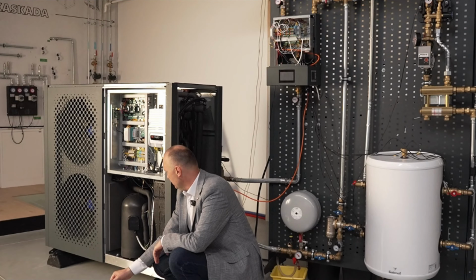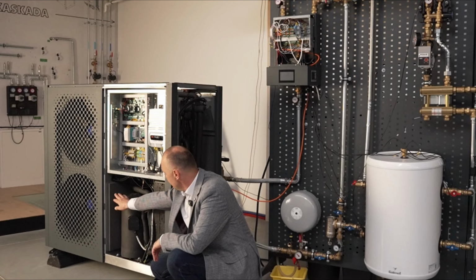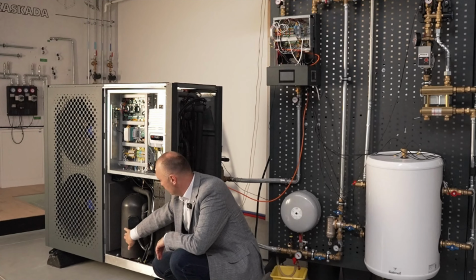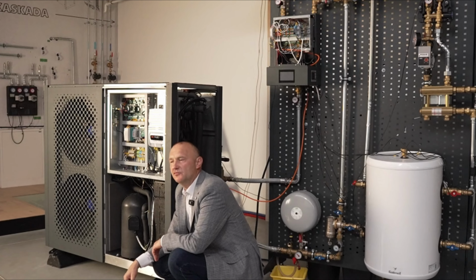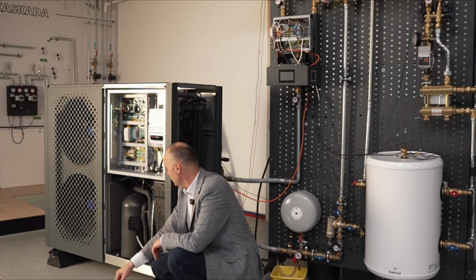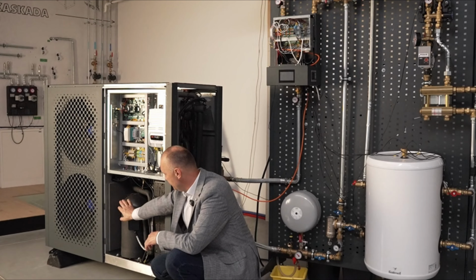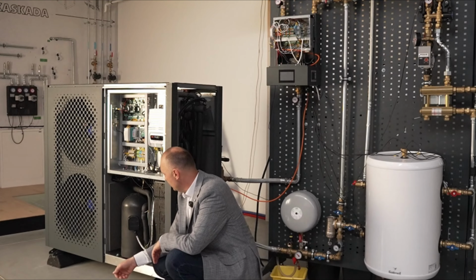So this represents a highly effective compressor design which performs exceptionally well within heat pump systems, particularly for heat pumps operating in extremely harsh environments, those that frequently need to undergo defrosting cycles and function reliably in very low ambient temperatures throughout winter. The compressor itself is encased in a special acoustic enclosure, which is known as the sound shell. Its primary purpose is to completely eliminate the noise generated by the compressor, but also to retain a significant portion of the heat within the compressor unit itself, so that as little as possible is emitted into the surrounding environment.